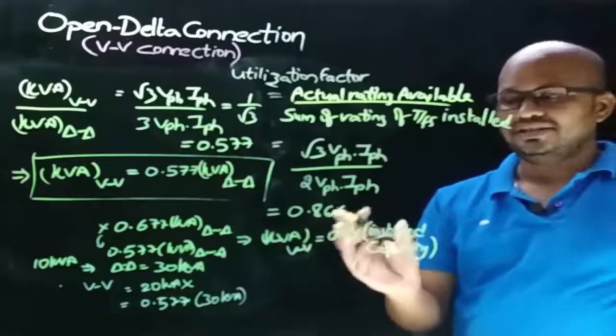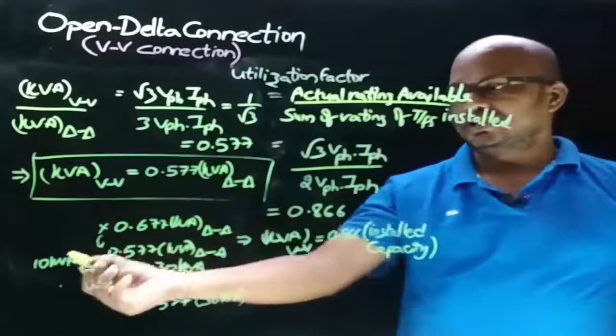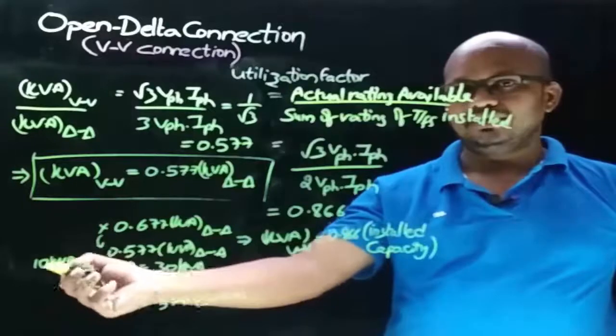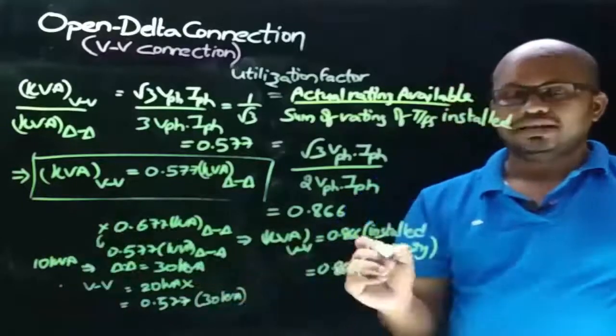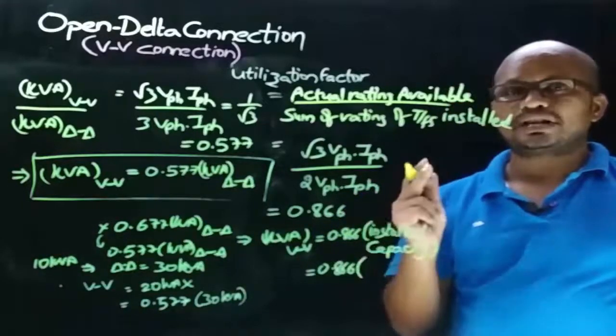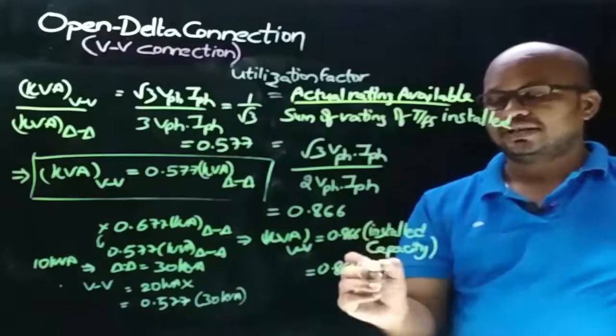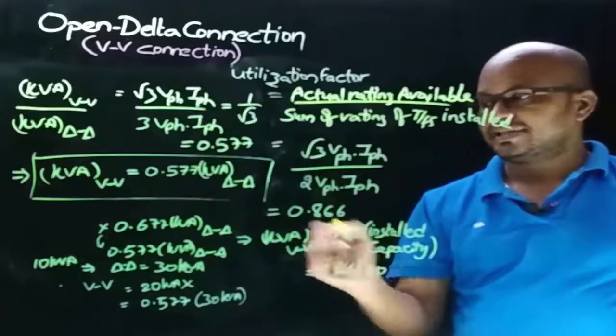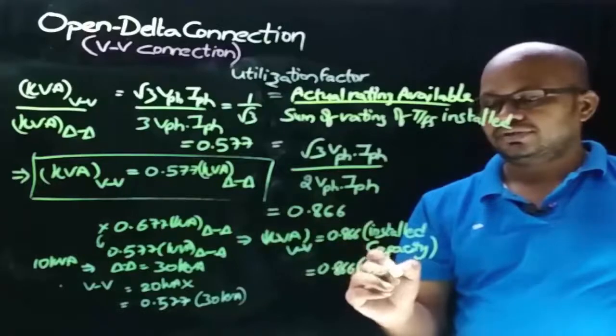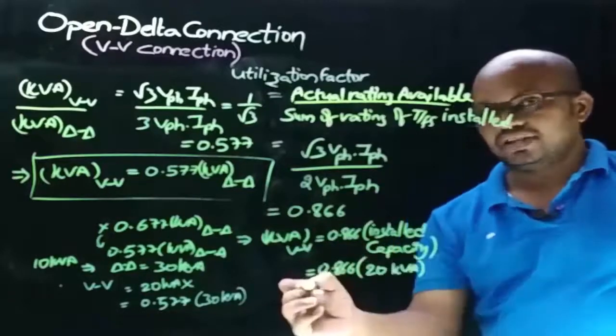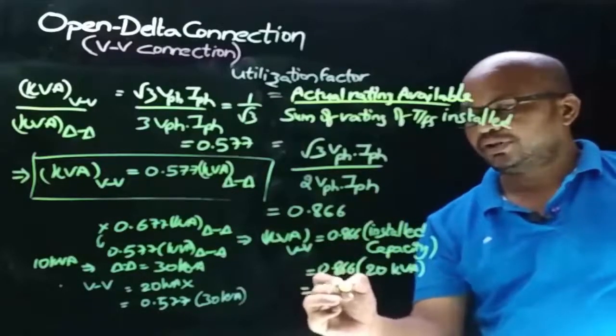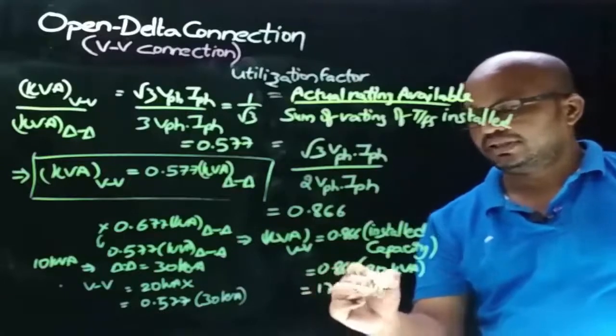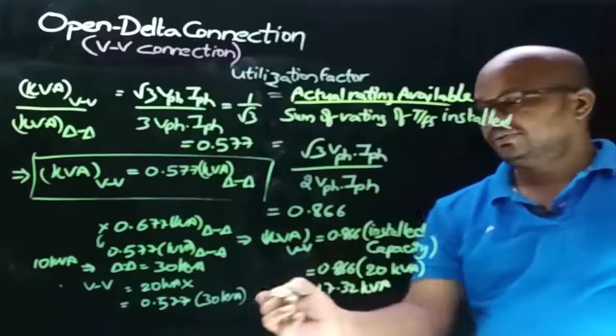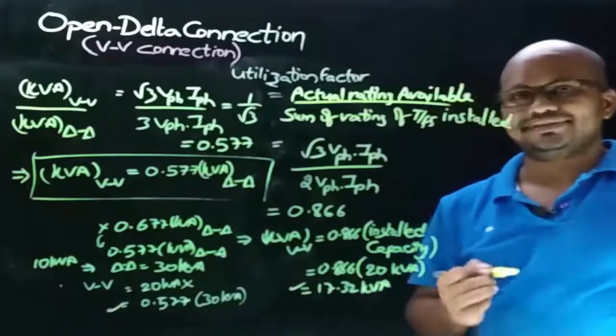And let's understand this with an example. We consider each transformer rating is 10 kVA, and as in open delta connection there are 2 transformers installed, so the installed capacity will be, from the example, 20 kVA. That will give you 17.32 kVA. This value and this value are the same.